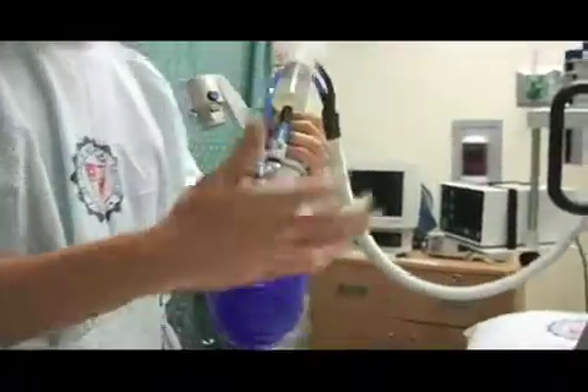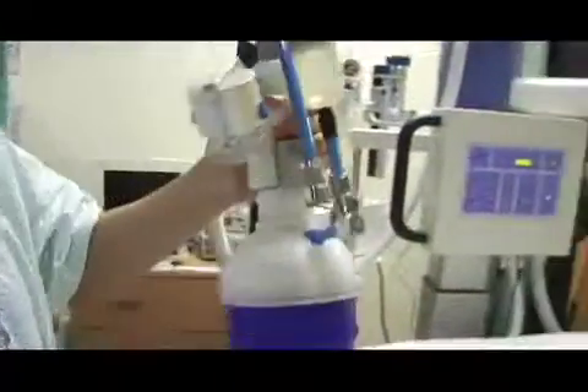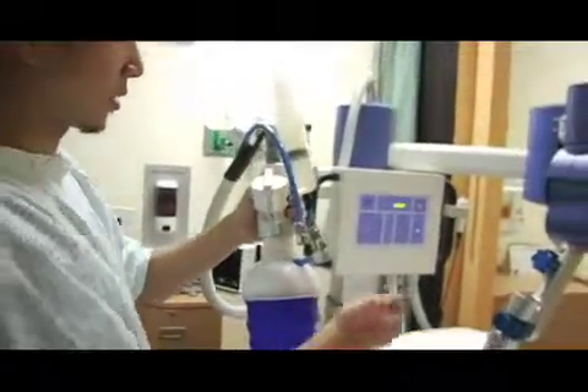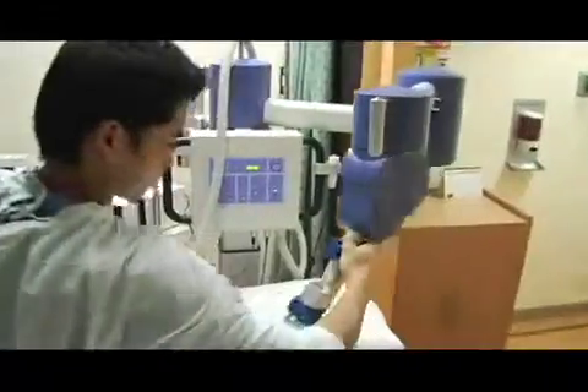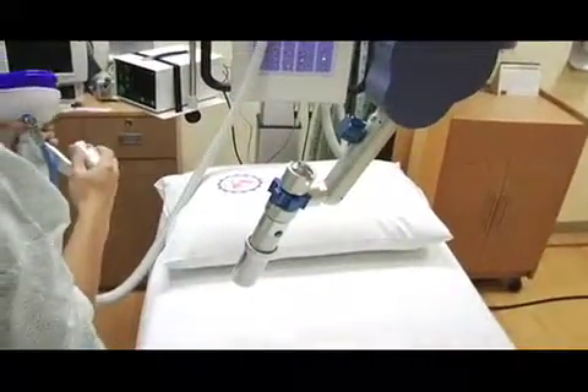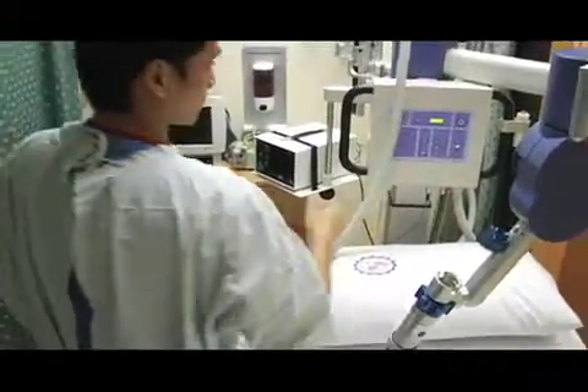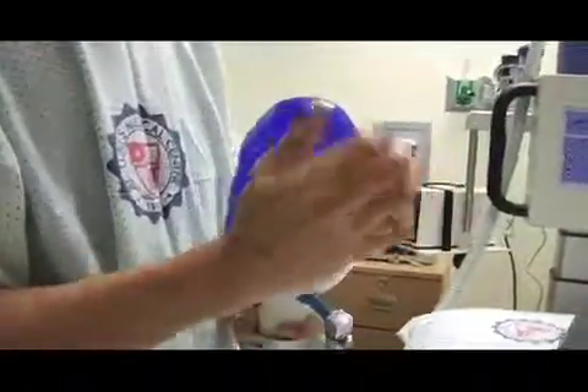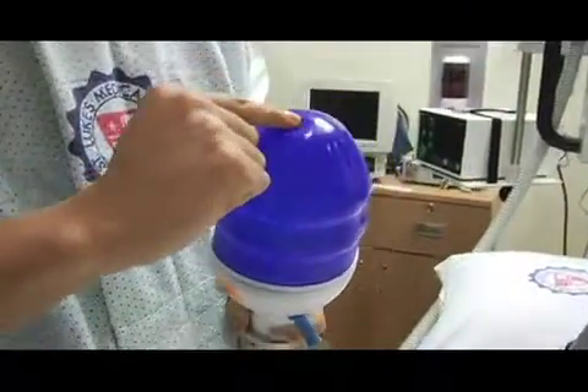That's why it is very important to remove the air inside the applicator for optimal generation of energy. Checking the machine prior to the procedure is essential to its efficiency, making sure that there is no bubble in the shockwave applicator.